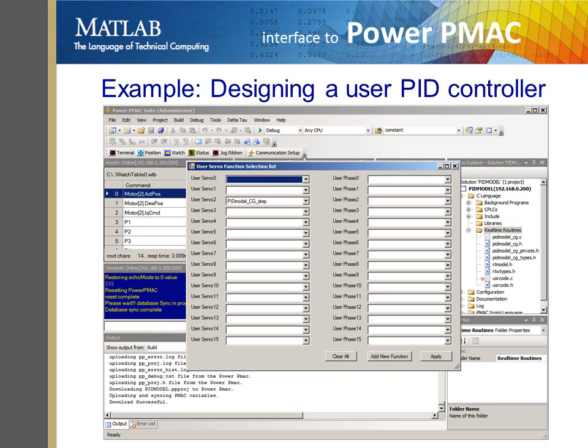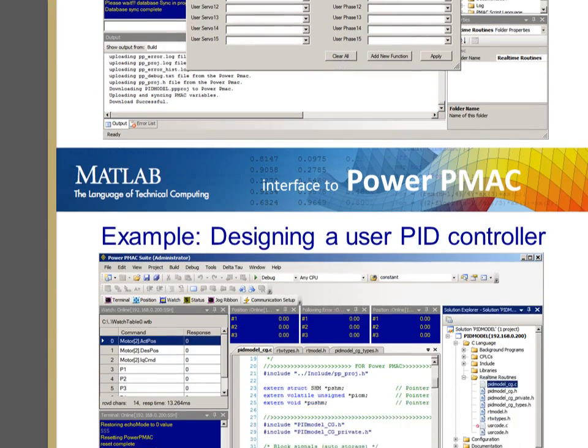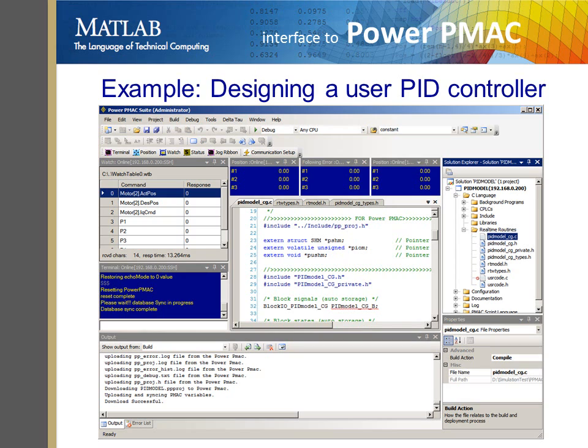Next, the user servo routine's step function needs to be assigned to the specific motor of interest. The IDE project may include other components like motion programs or PLCs that can be loaded at any time. After the project setup is complete, it can be built and downloaded to the PowerPMAC.